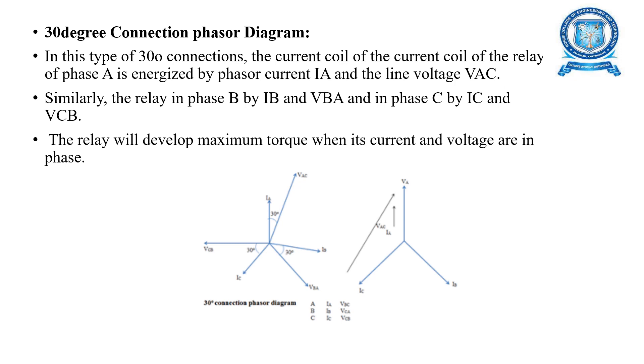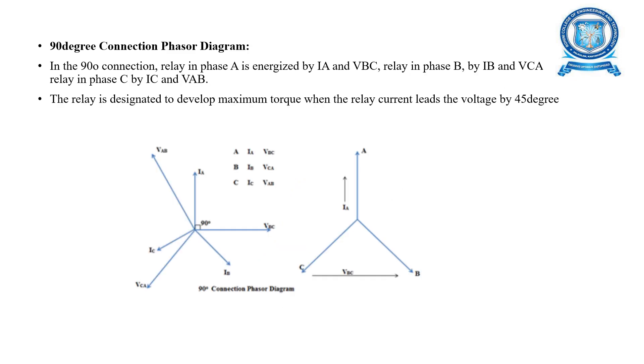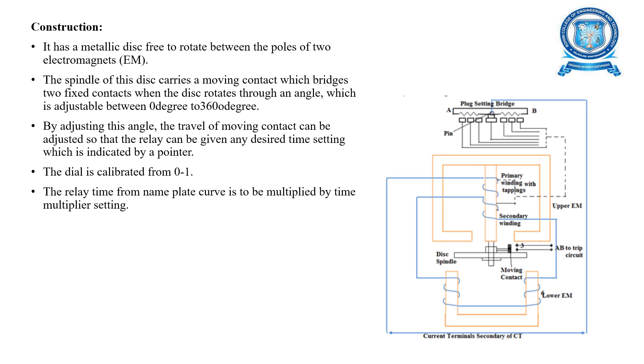Next is the 90-degree connection phasor diagram. Here the relay for phase A is energized by IA and VBC, the relay for phase B by IB and VCA, and the relay for phase C by IC and VAB. This relay is designed to develop maximum torque when the relay current leads the voltage by 45 degrees. This is the diagram for the 90-degree connection phasor diagram.